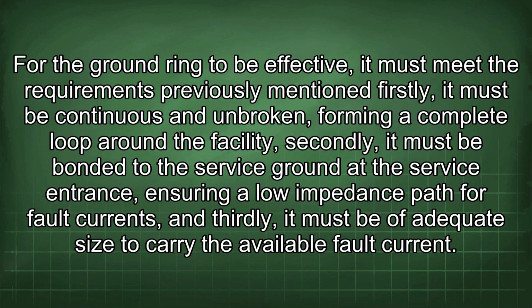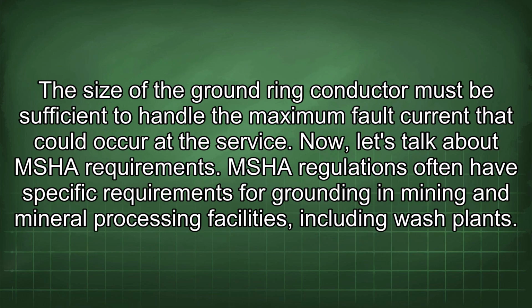For the ground ring to be effective, it must meet the requirements previously mentioned. Firstly, it must be continuous and unbroken, forming a complete loop around the facility. Secondly, it must be bonded to the service ground at the service entrance, ensuring a low impedance path for fault currents. And thirdly, it must be of adequate size to carry the available fault current. The size of the ground ring conductor must be sufficient to handle the maximum fault current that could occur at the service. Now let's talk about MSHA requirements.